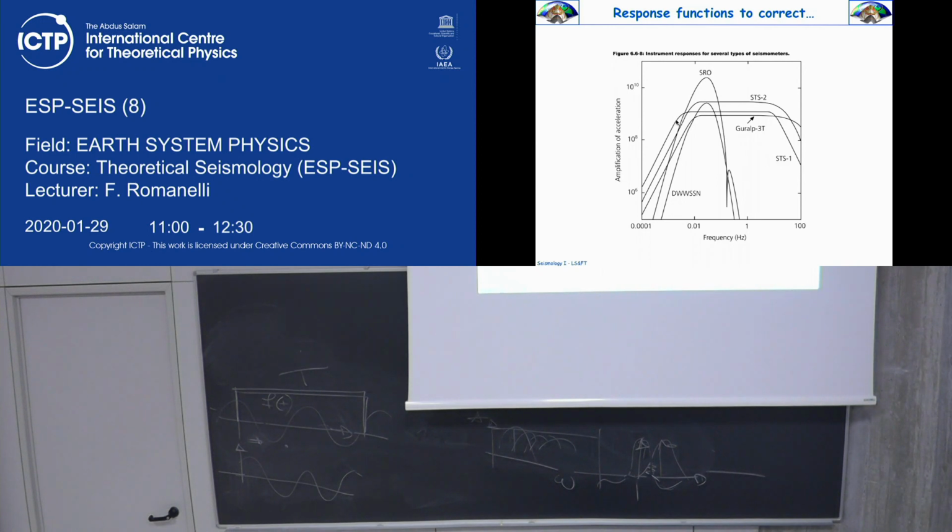For example, for very high frequencies, it's better to use accelerometers, because you know that acceleration is, okay, high school physics. Every time that you make a time derivative, you're taking out i omega for velocity, minus omega squared for acceleration. So the signal in acceleration is much richer in high frequencies than displacement. That's natural. High frequencies means that maybe if you want to record 100 Hertz, you can use accelerometers.